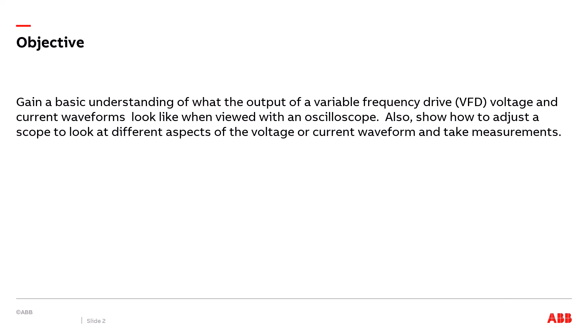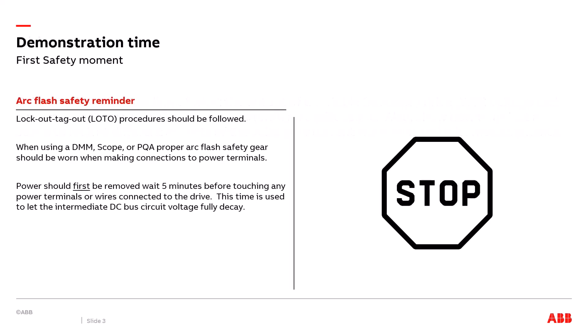We'll show how to use a scope to take measurements of these signals, such as voltage AC or current AC, and also measurements on the voltage waveform such as rise time or peak voltage. Before diving in, I want to remind everyone: arc flash safety is very important for all lockout/tagout procedures when making connections between a scope or meter and the VFD. It's best to wait five minutes once power is removed before making any connections to the drive.